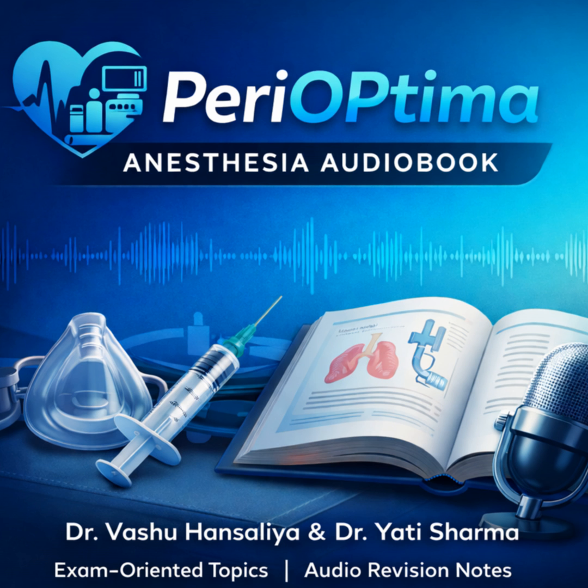You can autoclave them, typically up to 40 times, but there is a massive exam trap here that catches so many students. You must fully deflate the cuff before putting it in the autoclave. Why? What happens if you don't? Physics again. Boyle's law, PV equals nRT. If there's any residual air left in that cuff, when the temperature inside the autoclave rises to 121 or 134 degrees, that trapped air will expand dramatically.